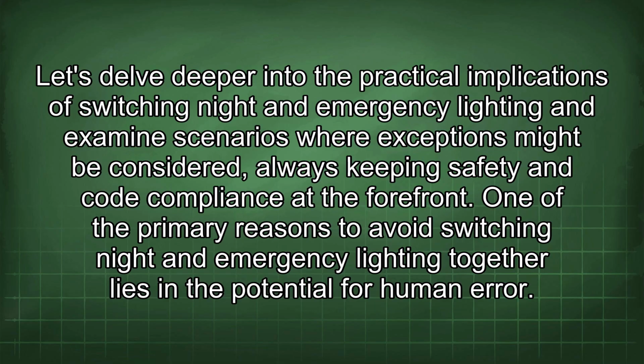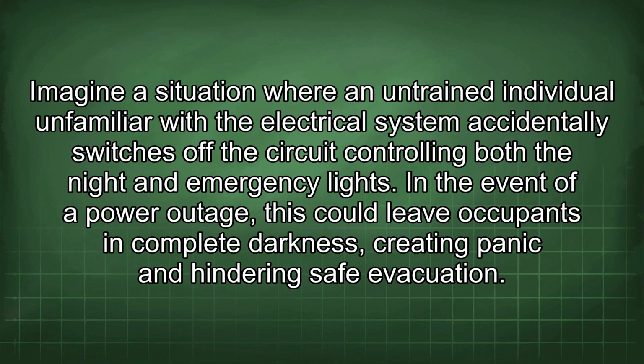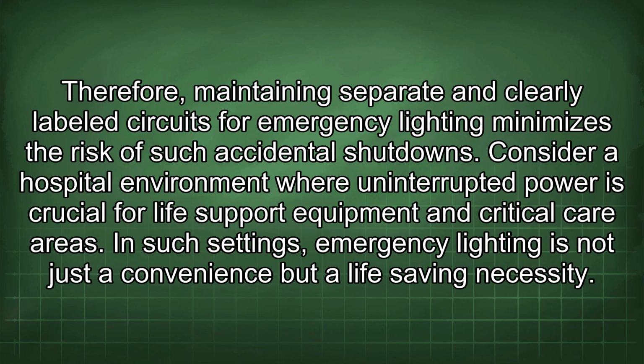One of the primary reasons to avoid switching night and emergency lighting together lies in the potential for human error. Imagine a situation where an untrained individual unfamiliar with the electrical system accidentally switches off the circuit controlling both the night and emergency lights. In the event of a power outage, this could leave occupants in complete darkness, creating panic and hindering safe evacuation. Therefore, maintaining separate and clearly labeled circuits for emergency lighting minimizes the risk of such accidental shutdowns.